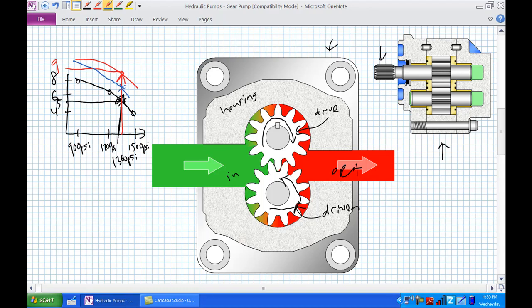You can think about it as, here is its nameplate value of 8 gallons per minute, and you can expect it to not be as good. All right, that's about it for our external gear pumps. Just a schematic time here. If you see a pump symbol that has no modifications to it whatsoever, it's a fixed displacement pump. Whereas this is a variable displacement pump, which we're going to go into next, one of the first of the two that we'll discuss.